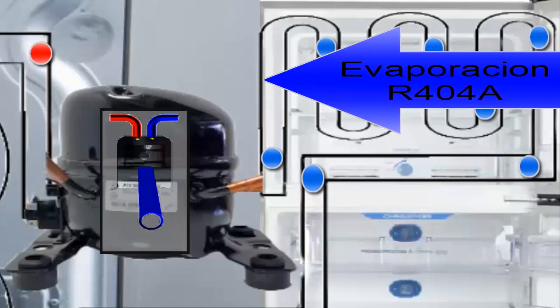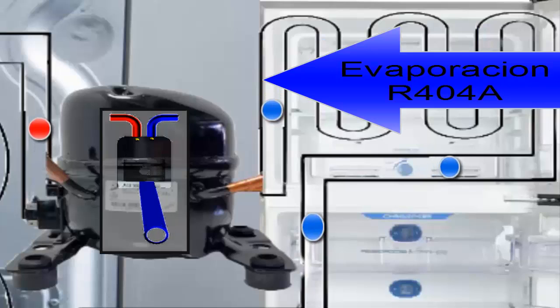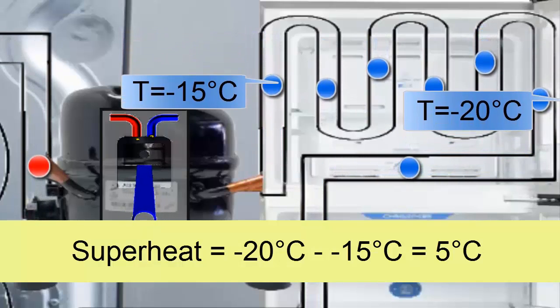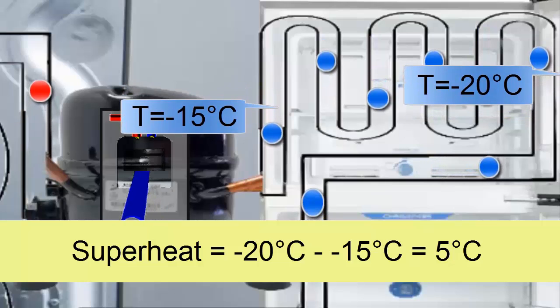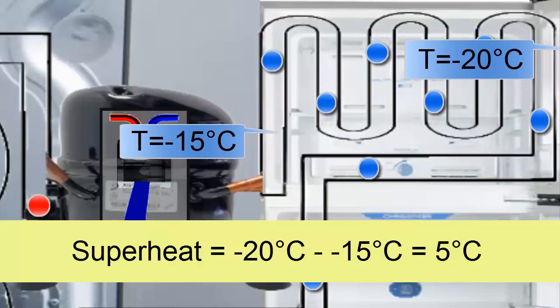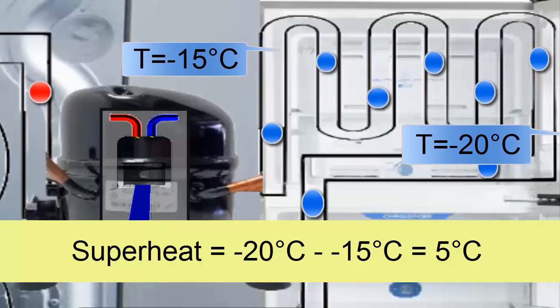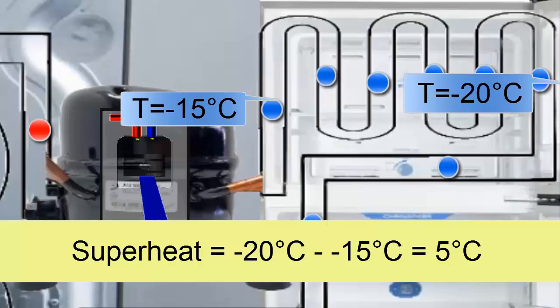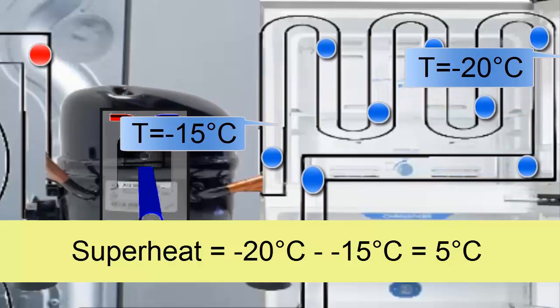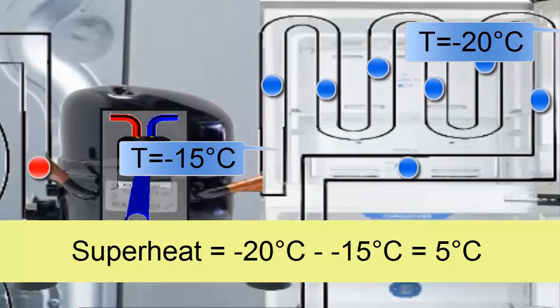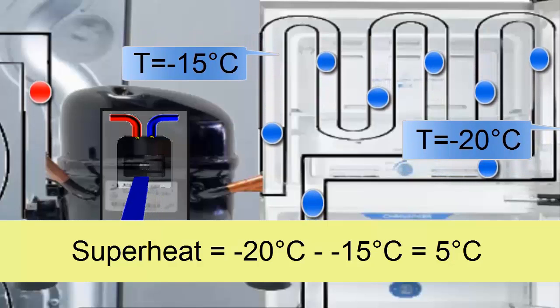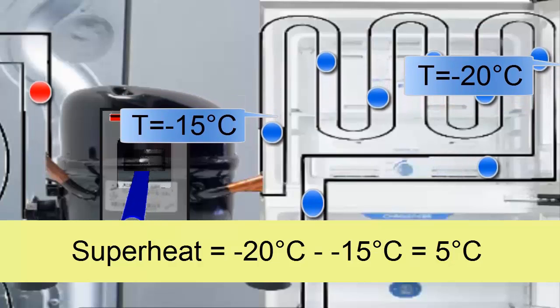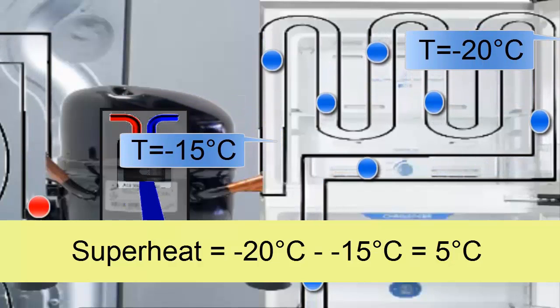The R404A, now in a gaseous state and with a slight temperature increase called superheat, is suctioned by the compressor. For this case, let's assume that the temperature of the R404A refrigerant in a gaseous state is minus 15 degrees Celsius. This means that the R404A refrigerant goes from minus 20 degrees Celsius to minus 15 degrees Celsius, so in this equipment the superheat is 5 degrees Celsius.